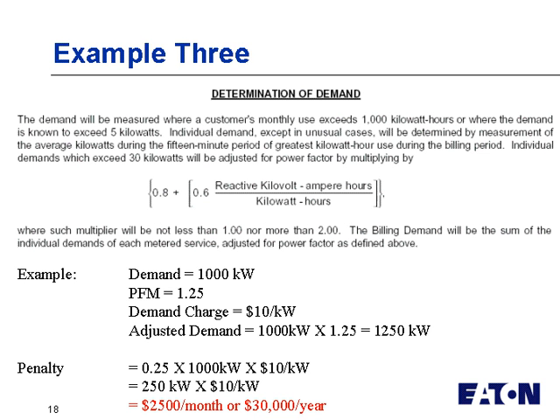That was the one I pointed out earlier. And if the power factor multiplier from this crazy equation comes up and it says that you're going to pay 1.25, that's again like a 25% penalty. So you're going to pay 250 kW more in this case than you would. So you're paying 1250 kW worth of demand rather than 1,000, which you're using, and that's a $30,000 a year penalty.